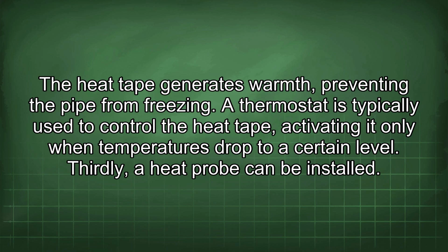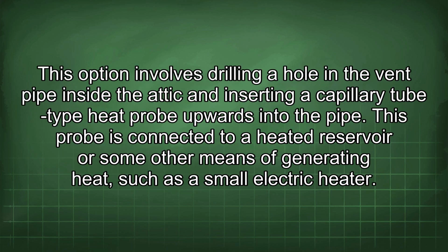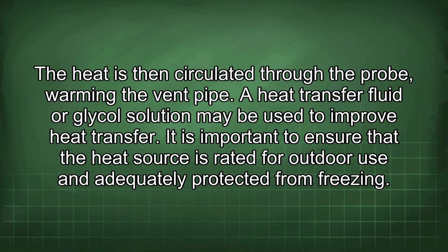Thirdly, a heat probe can be installed. This option involves drilling a hole in the vent pipe inside the attic and inserting a capillary tube-type heat probe upwards into the pipe. This probe is connected to a heated reservoir or some other means of generating heat, such as a small electric heater. The heat is then circulated through the probe, warming the vent pipe. A heat transfer fluid or glycol solution may be used to improve heat transfer. It is important to ensure that the heat source is rated for outdoor use and adequately protected from freezing.